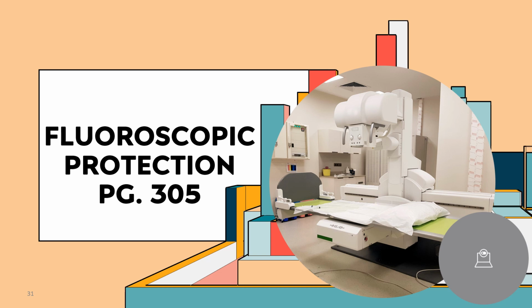So there are other means that help to reduce radiation dose. They are the beam collimation, added filtration, control of the exposures, the appropriate source to skin distance, and the protective housing. Now, the federal government also requires that there be a cumulative timer of 5 minutes with an audible alarm. And the source to skin distance for a fixed fluoroscopic unit is 38 centimeters or about 15 inches. A remote control system helps also to reduce the dose, so if you could use one, that is also recommended. The protective curtain coming off the image intensifier should be a minimum of 0.25 millimeters of lead and should not be removed. The Bucky slot cover is 0.25 millimeters of lead.